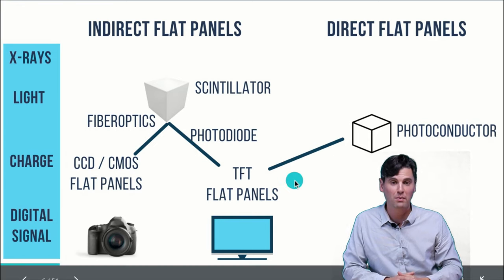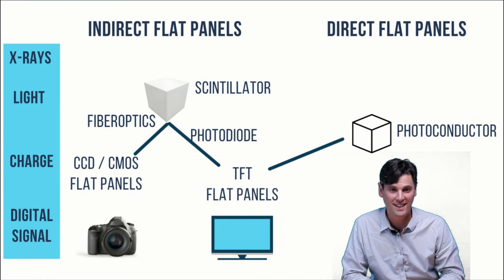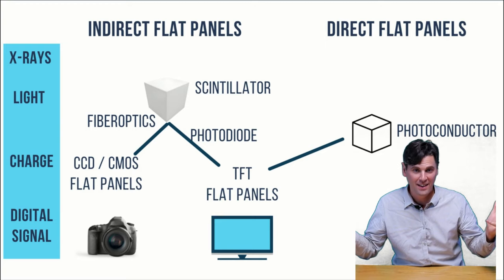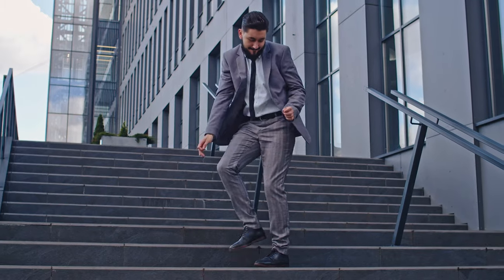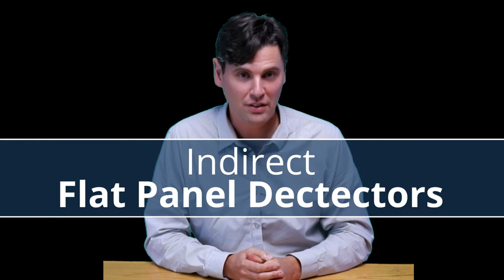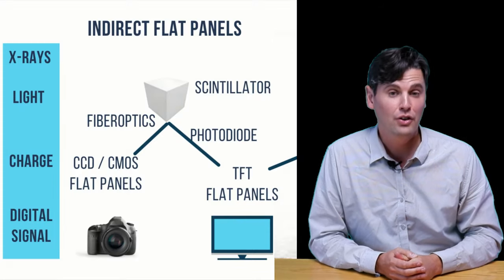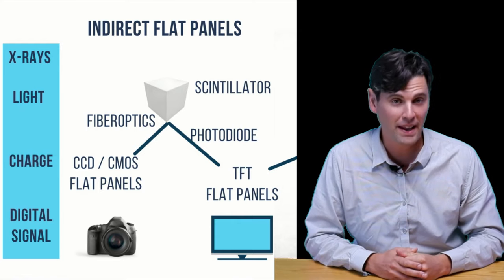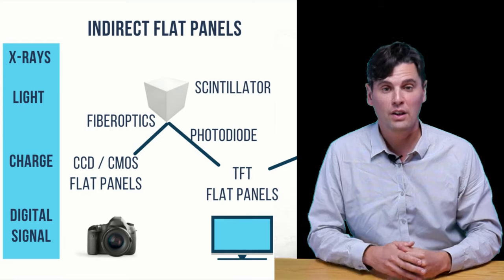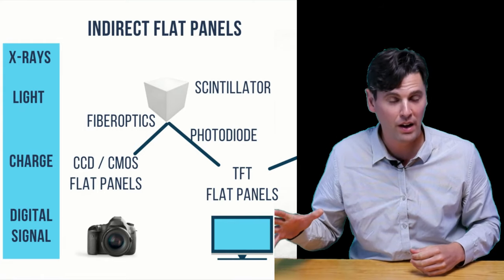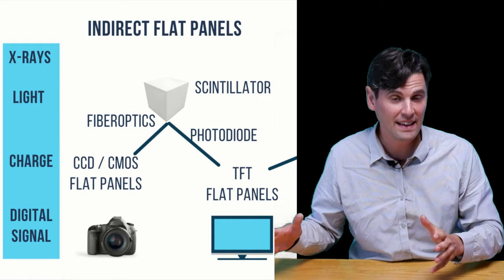Direct versus indirect — those are two different types of flat panels. With direct, you're skipping a step; with indirect, you have an extra step, and that extra step is generating light. We'll cover indirect flat panels first because those are more frequently seen within the clinic. Indirect flat panels also have two different types depending on how they're read out — either a TFT or a CCD.